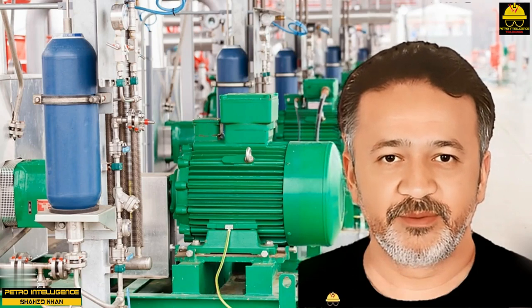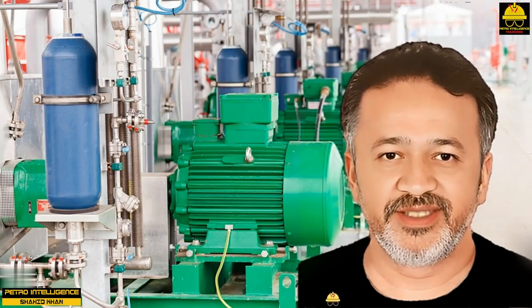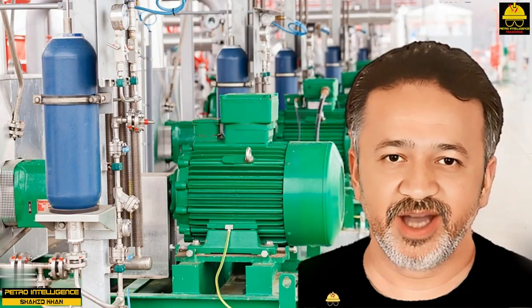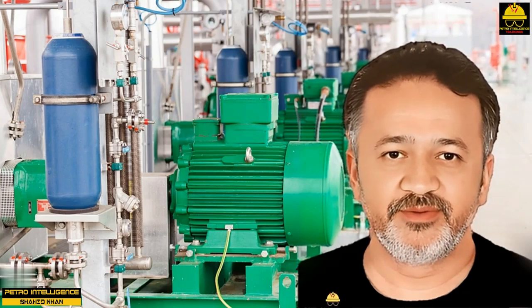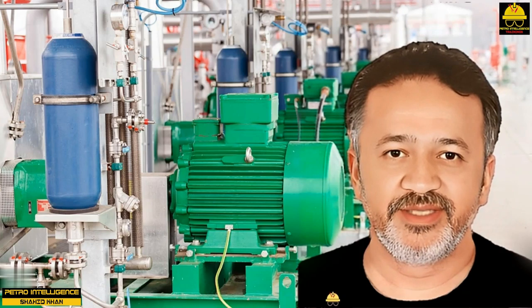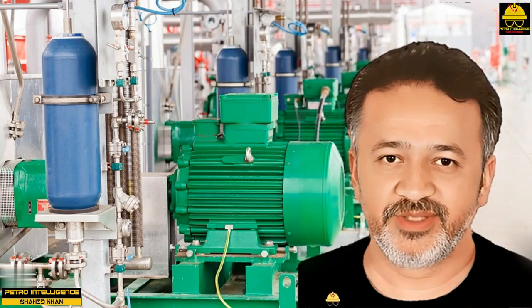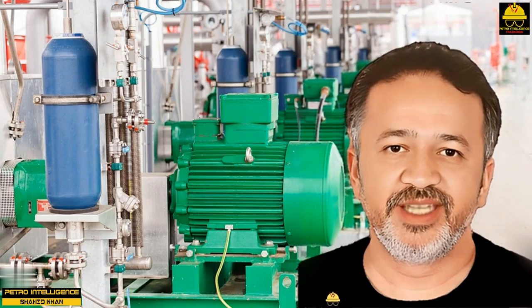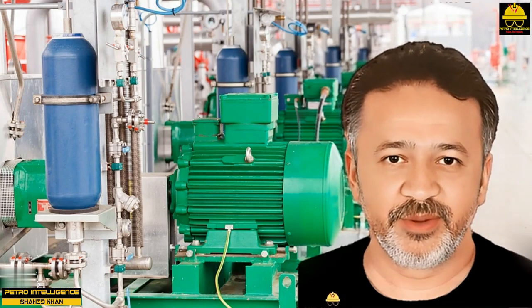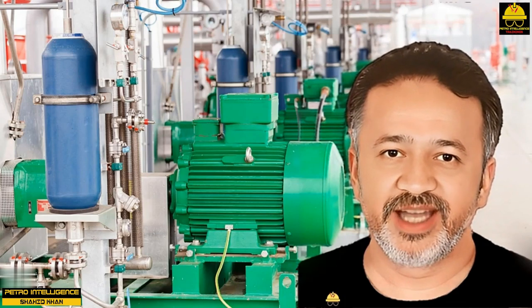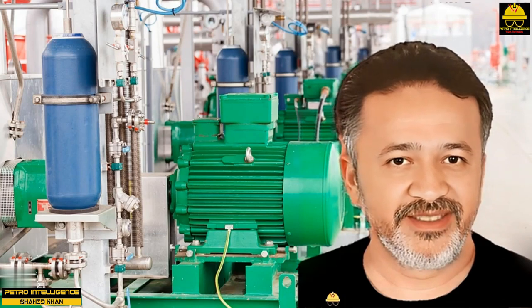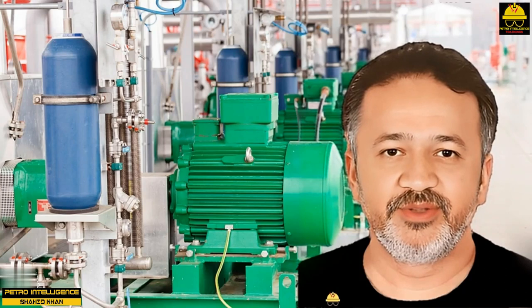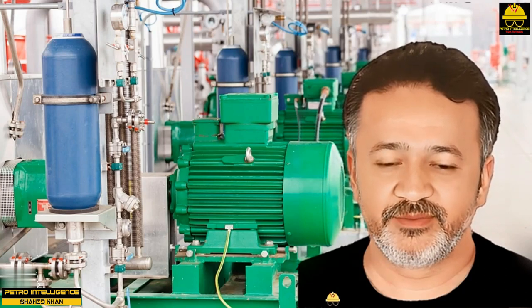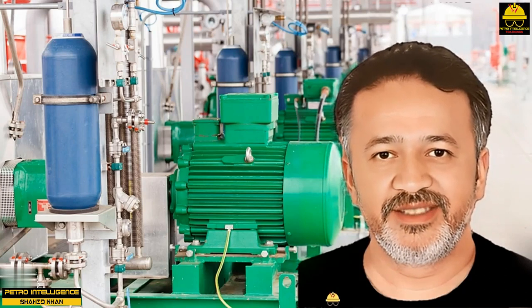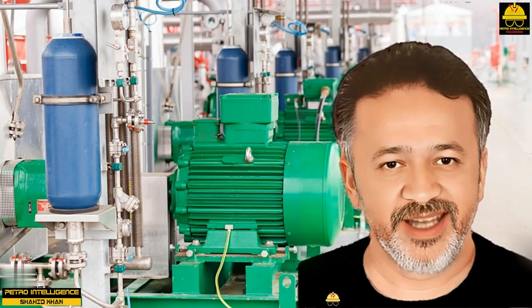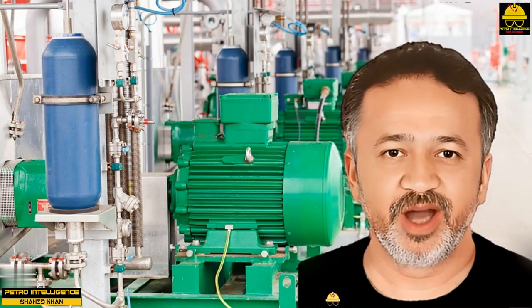They deliver liquid when a piston, plunger, or diaphragm physically displaces it. The diaphragm, piston, or plunger pushes the fluid as it moves back and forth inside a cylinder or housing. The suction system requirements for a reciprocating pump are similar to those of other pumps except for one important factor: acceleration head. Acceleration head takes into account the back and forth inertia that a reciprocating pump creates. Acceleration head is defined as the fluctuations of suction pressure created by the intake stroke of a reciprocating pump.